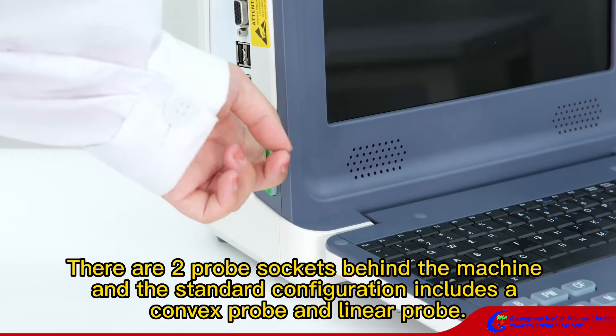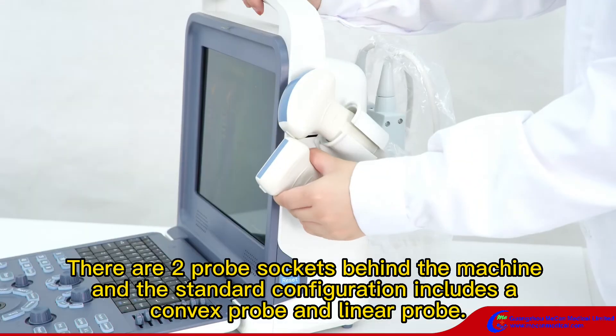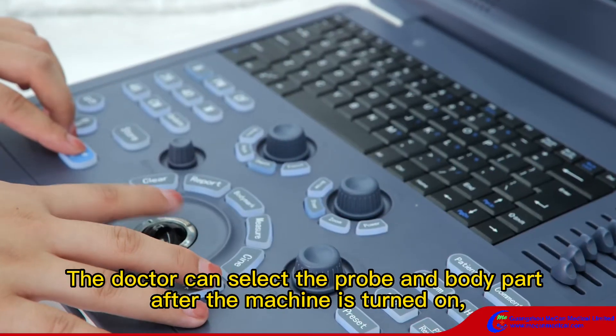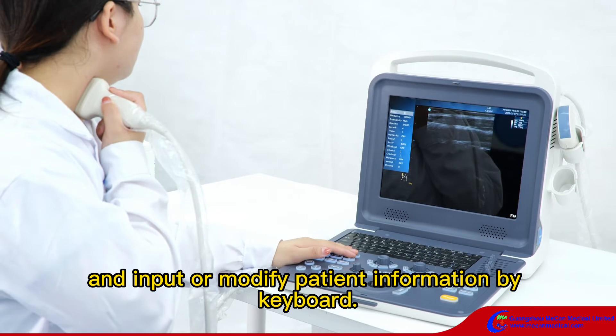There are two probe sockets behind the machine and the standard configuration includes a convex probe and a linear probe. The doctor can select the probe and the body part after the machine is turned on, and input or modify patient information by keyboard.